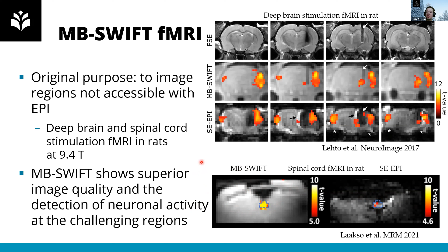One third of the brain is gone because of the image distortions caused by the electrode. But in the MB-SWIFT image, the novel approach, we just see this clean line for the electrode, and then we can also see the activation at the electrode tip and at the projection sites in the cortex. In this lower example, we have spinal cord fMRI in rats. This is the EPI image. It's very blurry, very distorted, and you can barely guess where the spinal cord is. It should be where the blue dashed line is, and these colored pixels tell where the activation to the spinal cord stimulation occurred. But if we look at the novel approach, we have a clean image with basically no distortions, and we can clearly see the activation in the spinal cord due to the stimulation. So overall, the novel method shows superior image quality compared to EPI in these challenging circumstances.